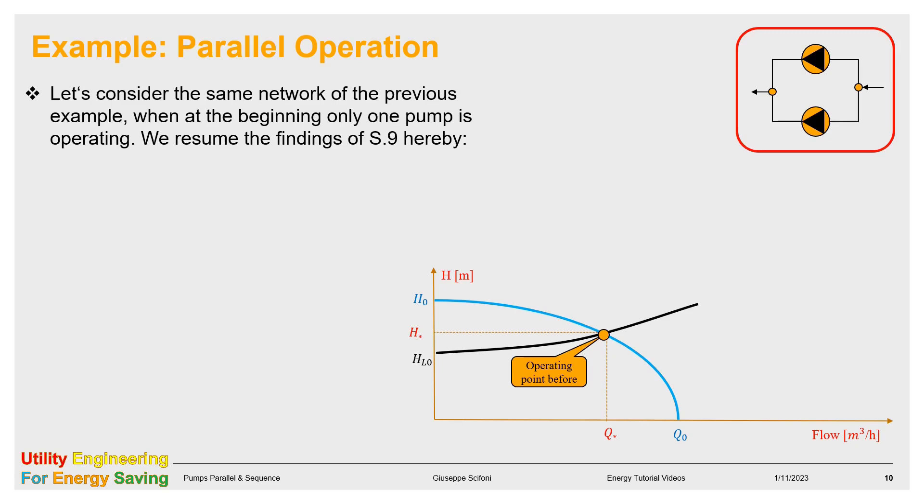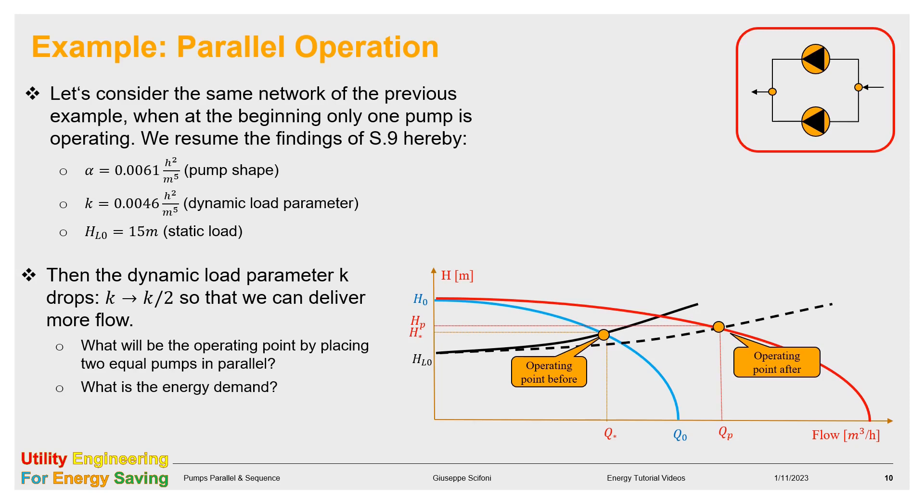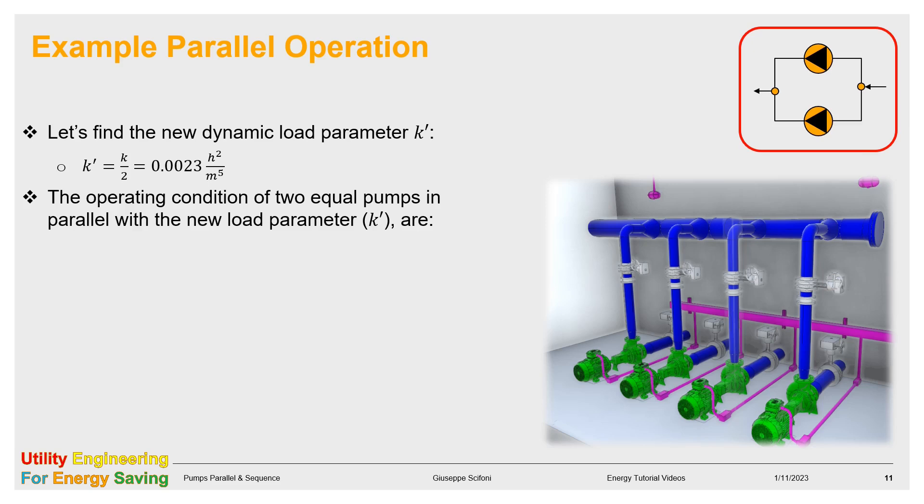For the parallel operation example, we keep the same network of the previous example when only one pump was operating. Let's resume here by the findings of slide number 9. We assume now that the dynamic load parameter K drops to the half and we want to deliver more flow by adding a second equal pump in parallel. Questions are the same of previous problem under changed conditions. The new dynamic load parameter K' is the half of K, also 0.0023.